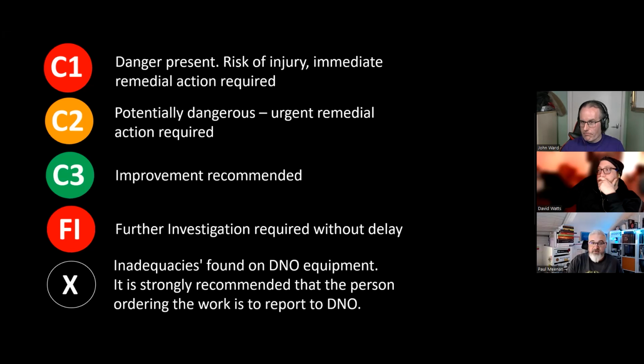Inadequacies found on DNO equipment. It is strongly recommended that the person ordering the work is to report to DNO. So this has not been spoken about today at all, or the last 2 days. Very, very controversial. If we find an intake with live parts accessible, I'm assuming we would still C1 or C2 that. However, this is basically telling us that if you're finding a DNO where the lead wrap is melting pitch, as we saw earlier on, or it's a poor earthing configuration, it's not your problem. Put it down as an X and still pass it.